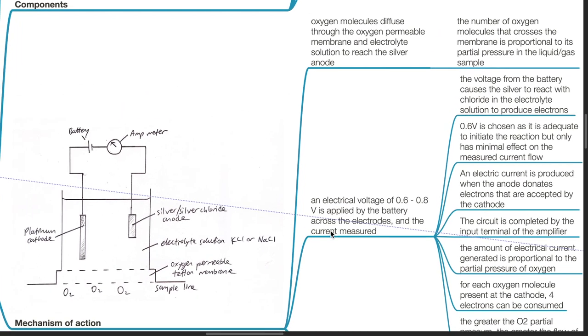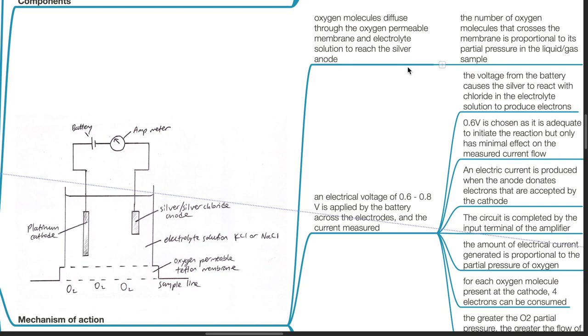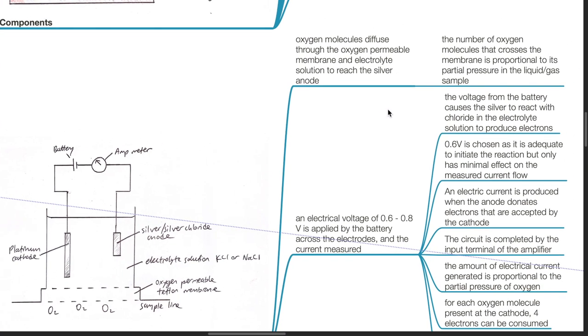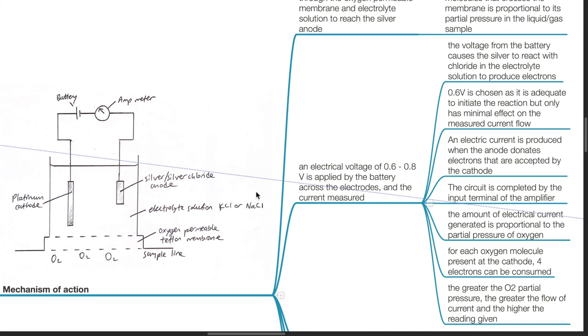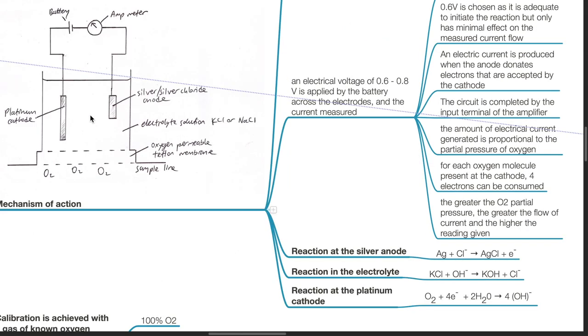Oxygen molecules diffuse through the oxygen-permeable membrane and electrolyte solution to reach the silver anode. The number of oxygen molecules that cross the membrane is proportional to its partial pressure in the liquid or gas sample. An electrical voltage of 0.6 to 0.8 volts is applied by the battery across the electrodes and the current is measured. The voltage causes the silver to react with chloride in the electrolyte solution to produce electrons. 0.6 volts is chosen as it is adequate to initiate the reaction but has only minimal effect on the measured current flow. An electric current is produced when the anode donates electrons that are accepted by the cathode, and the circuit is completed by the input terminal of the amplifier. For each oxygen molecule present at the cathode, 4 electrons can be consumed.